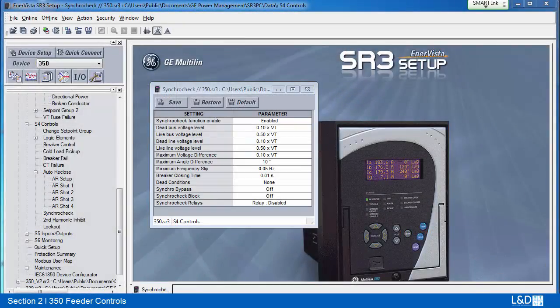Synchro-check element is used for monitoring the connection of two parts of a circuit by closing a breaker. This element verifies that the voltages VL and VB at both sides of the breaker are within the magnitude, angle, and frequency limits set by the user. VL and VB are the line and bus voltage values measured by the device. There must be the same VT connection on both sides to be compared on the same basis, either phase-to-phase or phase-to-ground. Synchro-check is normally executed under live line and bus conditions.